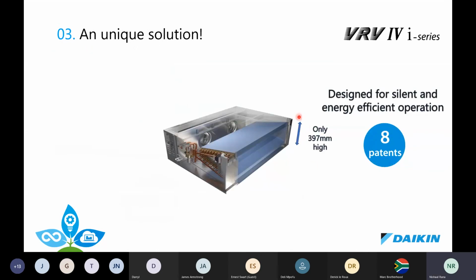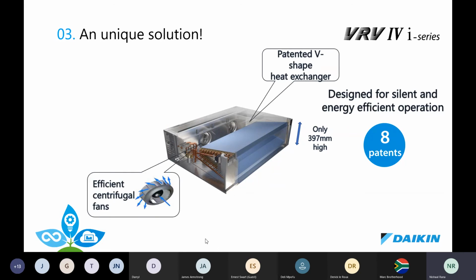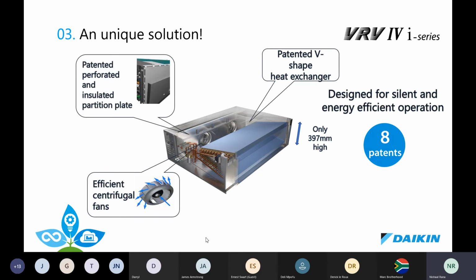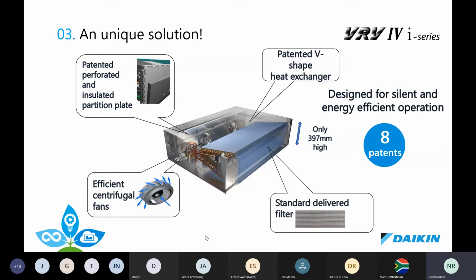The air module, which you would connect your inlet and outlet louvers to, is only approximately 400 millimeters high, and it's designed for silent operation. It's got a V-shaped heat exchanger, so better heat transfer, a centrifugal fan, so it's obviously quiet, and a patented, perforated and insulated partition plate to prevent backspill of air. You've got a standard filter on it. Be careful though, filters need to be cleaned. Remember, the dirtier your environment or where you're drawing in the new air from, the dirtier that filter will be.